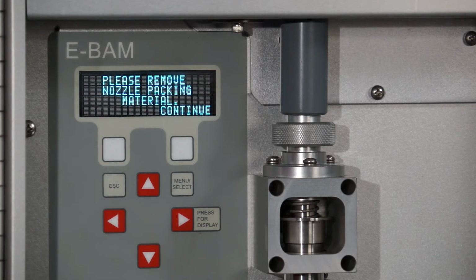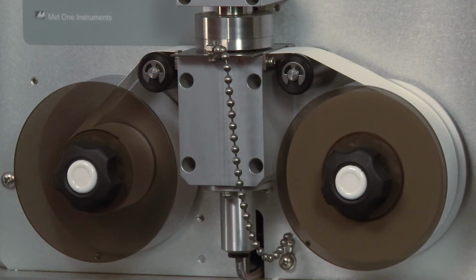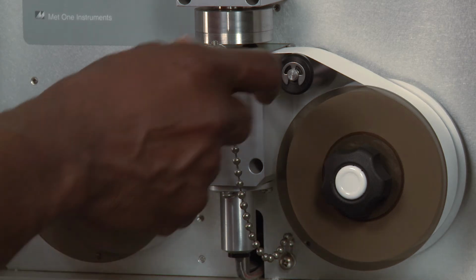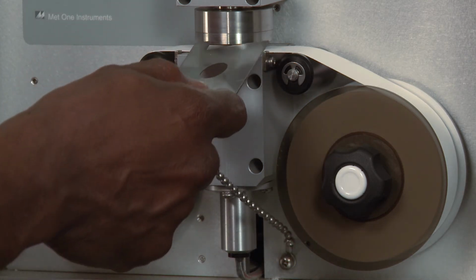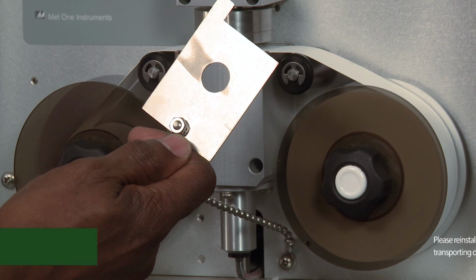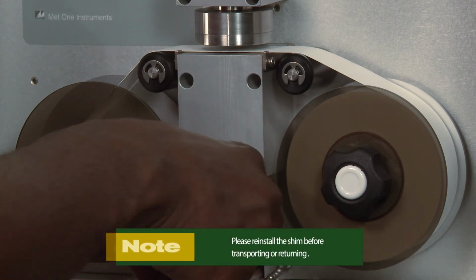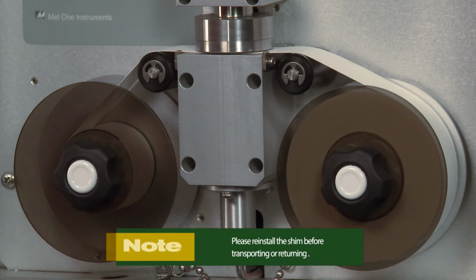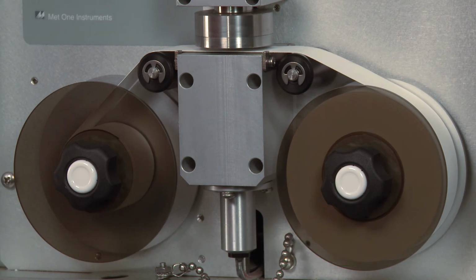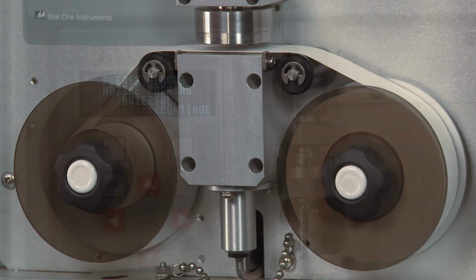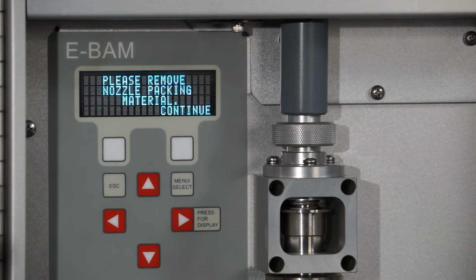Immediately after the machine type is set or verified, the EBAM automatically raises the nozzle and checks to see if the stainless steel shipping shim is installed under the nozzle. The shim is attached to the unit with a tether chain and is also used for the zero portion of the span membrane test. The shim should be installed anytime the EBAM is shipped or transported to prevent nozzle damage. The unit can sense the shim with a photo sensor. If the shim is still in place, the unit will display this message. Carefully remove the shim.